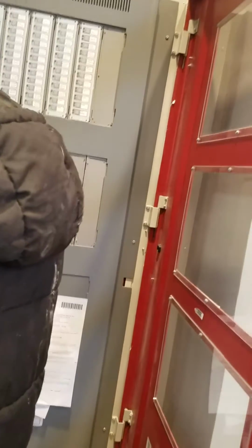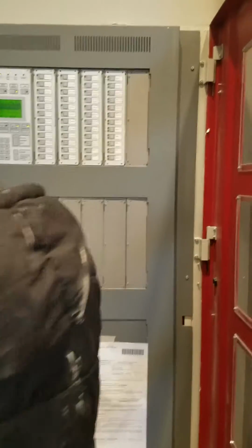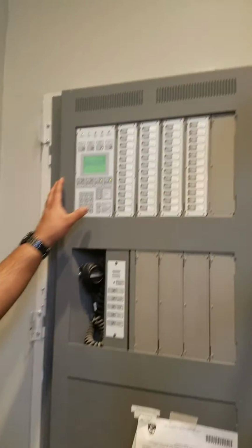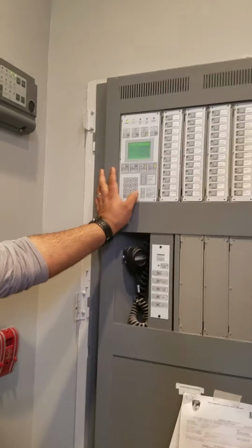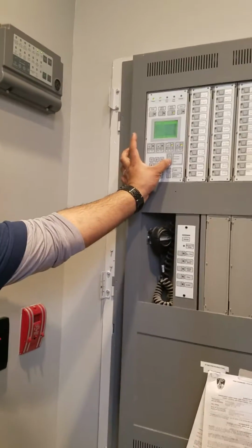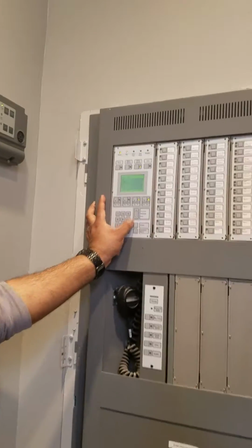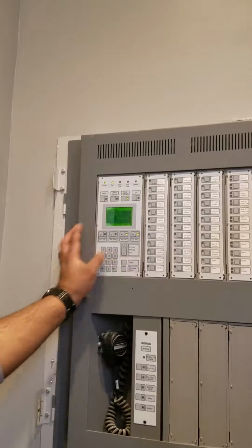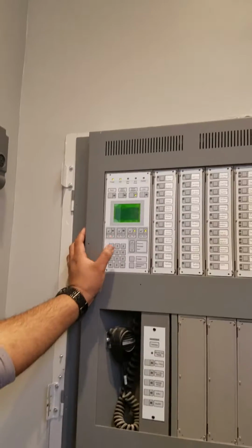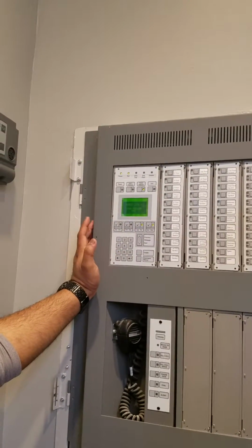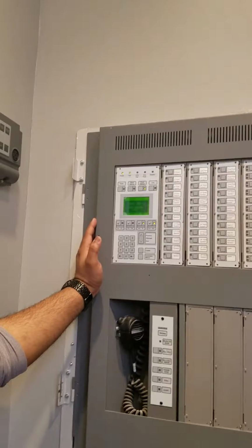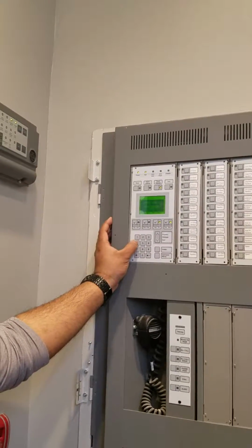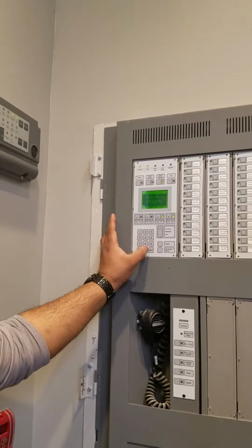I don't know if you want to take it off test mode so that it'll work this time. Oh, okay, yes, we can do that. So to cancel test mode, since we are on test, you would go to command menus. You would scroll down to test, which is 8. Select 8, and you want to cancel test, which is number 2. So you would see test group, and it would ask you for the access level 4 password. It kind of tells you the password, access level 4. So you would enter 4.